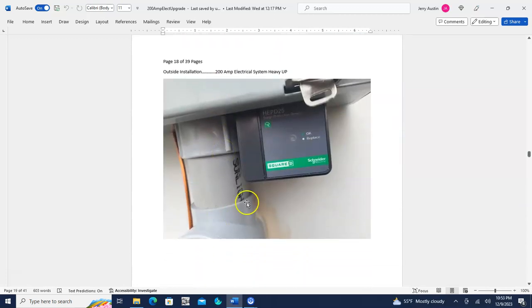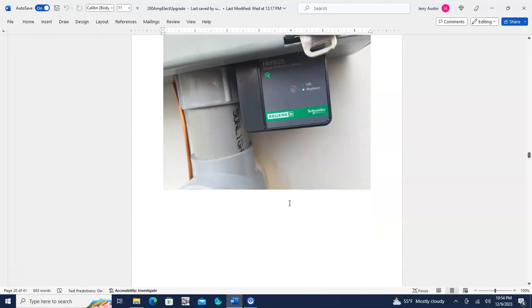More of the outside installation. This is a close-up of the, you can read it there, it says surge protector, surge protection device. And it's a Square D surge protection device, and it's got a little on-off switch inside this quick disconnect box. Right now it says it's okay, and if it ever needs to be replaced, that'll come on. You've got to undo this quick disconnect box and replace that. Cut off the power. Cut off those two switches inside the quick disconnect box and replace that.